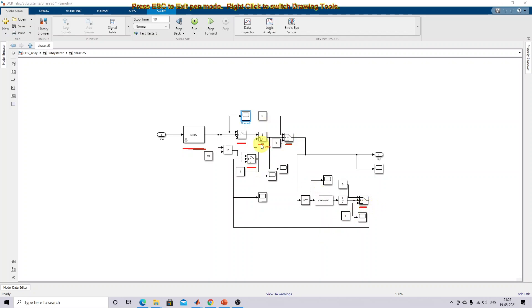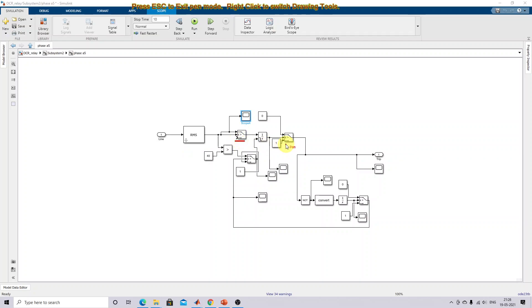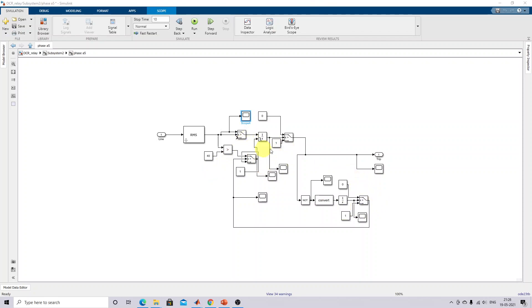You also have to use an integrator initially for switching of the overcurrent relay operation. These two switches are used for checking the overcurrent settings. Here the overcurrent setting is 40 amps — that is the maximum overcurrent setting. Beyond that current setting, if any fault causes the current to reach beyond this limit of 40 amps, the relay is going to open that circuit breaker.